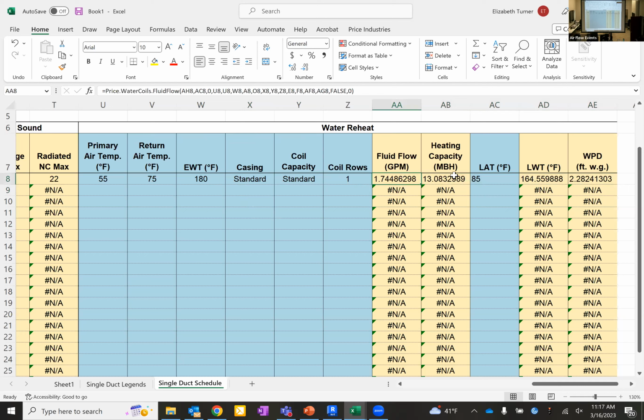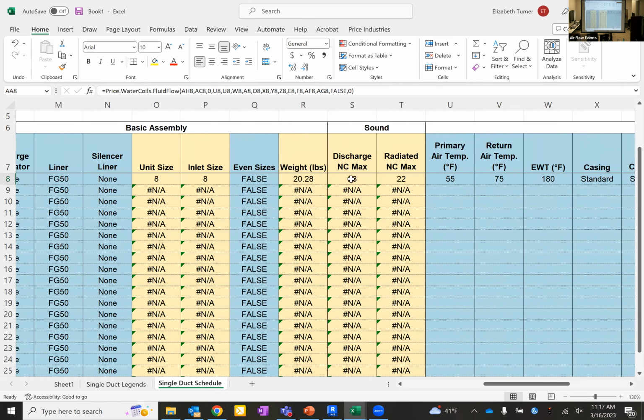So we have our fluid flow, heating capacity, leaving water temperature, fluid pressure drop, all of our water coil performance. It is also calculating our sound. So we've got our discharge and radiated NC levels, our unit weight, and it's auto calculating our unit size.